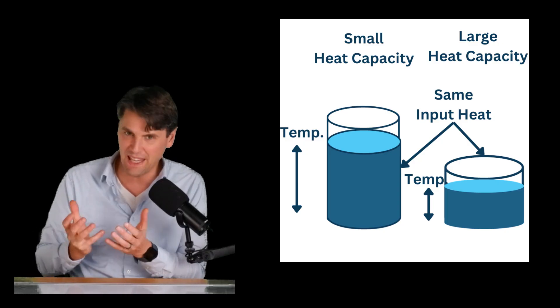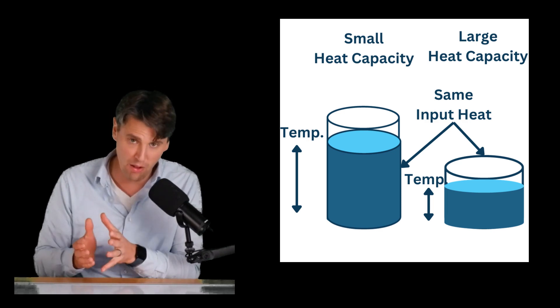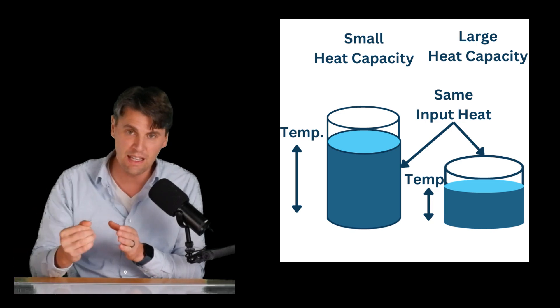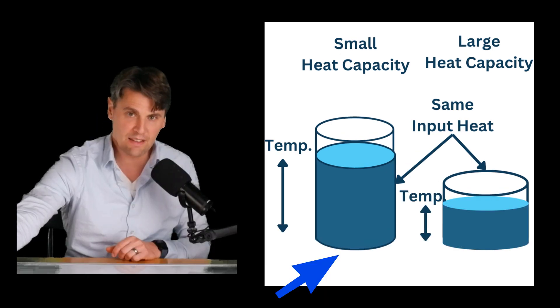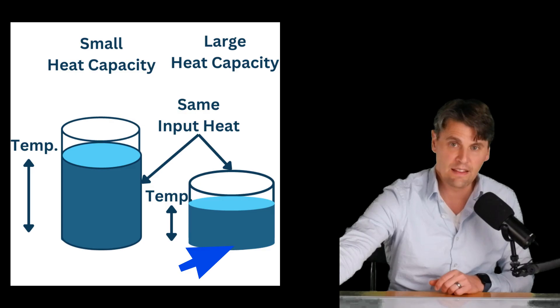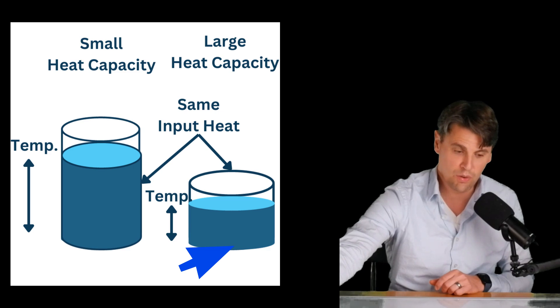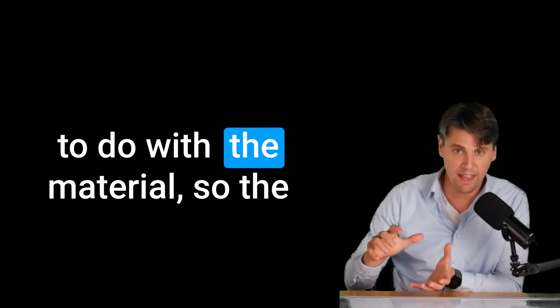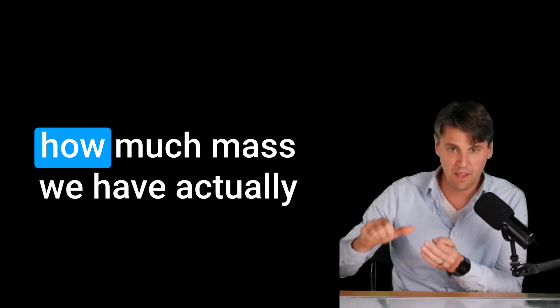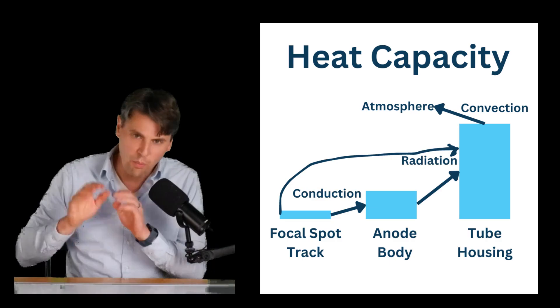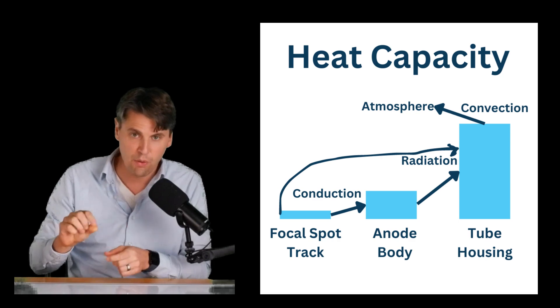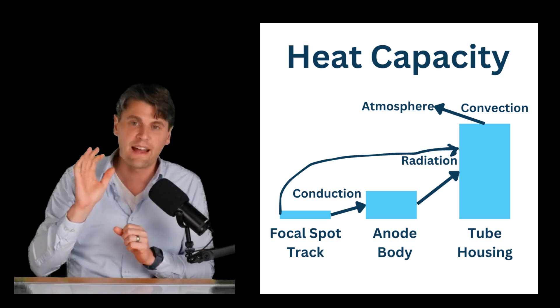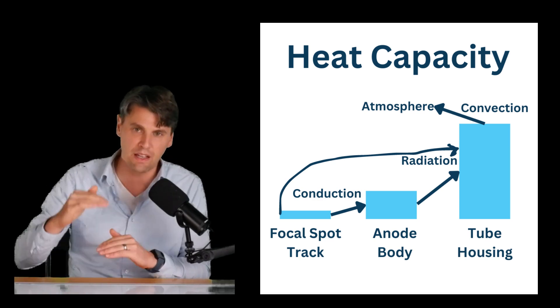What's the capacity to dump heat into this x-ray tube? If it has a relatively small heat capacity and you put the same amount of heat energy in, the temperature is going to go up a lot. As shown schematically here, in both cases we're adding the same heat. In one case it has a small heat capacity so the temperature goes up a lot; in the other it has a large heat capacity so the temperature only goes up a little bit. The heat capacity basically just has to do with the material — the specific heat of the material and how much mass we have to distribute that heat over.